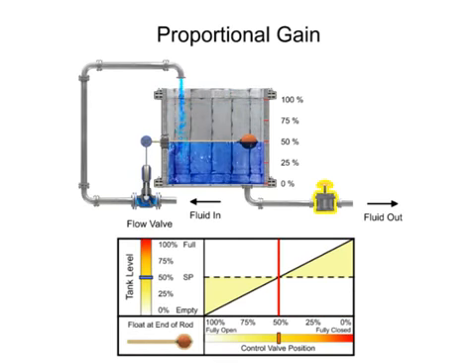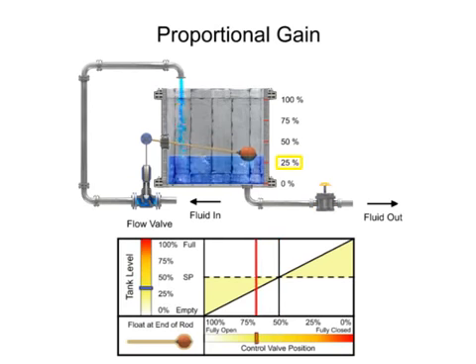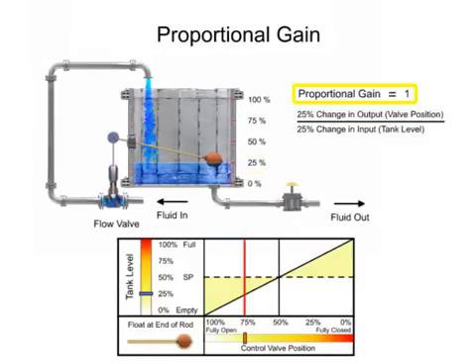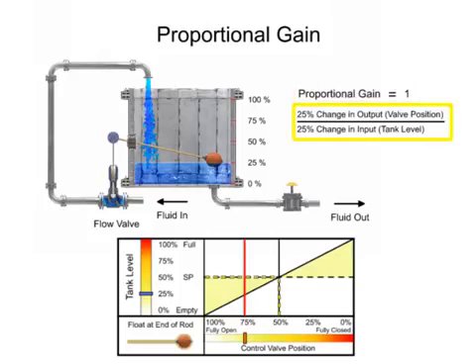Opening the drain valve increases the load demand, which causes the tank level to drop by 25%. The float drops and the valve opens 25%, which allows more fluid flow to enter the tank. A gain of 1 is demonstrated in this mechanism, since the 25% change of input or tank level results in a 25% change of output or valve position.